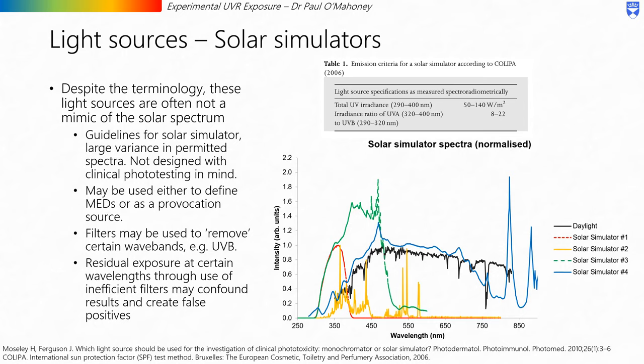Another type of light source is the solar simulator, which are typically broadband light sources. Despite the terminology, these light sources are often not a mimic of the solar spectrum, as is evident in the graph shown. There are guidelines for solar simulators, but they do permit a large variance in the spectrum and were not specifically designed with clinical phototesting in mind — as the reference shown indicates, the guidelines were designed with SPF measurement in mind. These light sources may be used to define MEDs or as a provocation source; however, the MED determined will be specific to that light source. Filters may sometimes be used to remove certain wavebands, for example UVB, although residual exposure at certain wavelengths through the use of inefficient filters may confound results and create false positives. This is a reminder to always look at both the spectral irradiance and the logarithmic spectral irradiance.